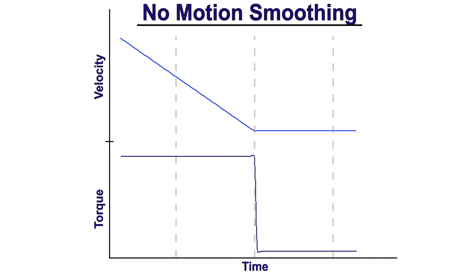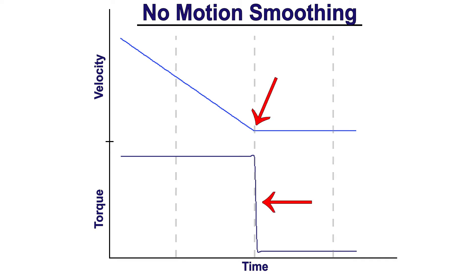If we look at this torque trace lined up with the trap move, you can see that as the motor is following the slanted trajectory in the velocity versus time profile - a constant deceleration rate - the torque is flat and constant, which makes sense. We're telling it to maintain a specific acceleration, so in the torque domain you're going to maintain a specific torque. But when we get to the point where we're going from deceleration to zero velocity, we see a straight vertical line - that's us telling the motor from a torque standpoint to instantaneously hit the brakes and stop.